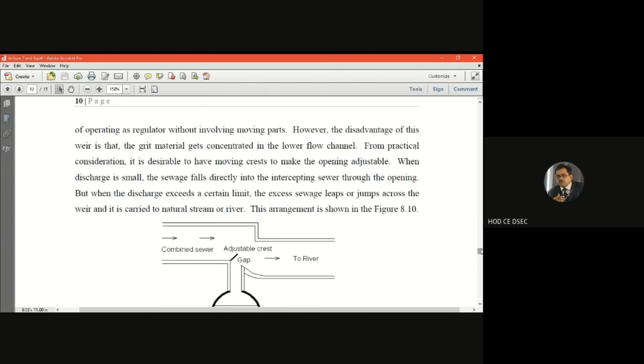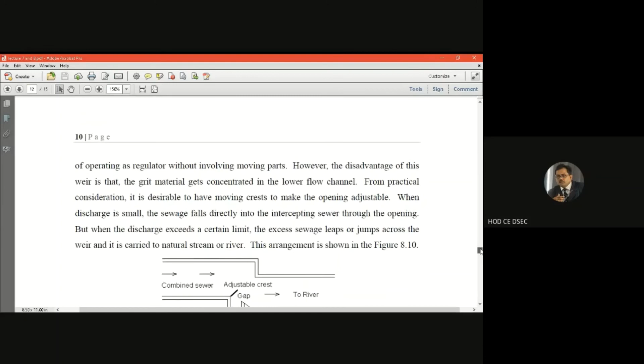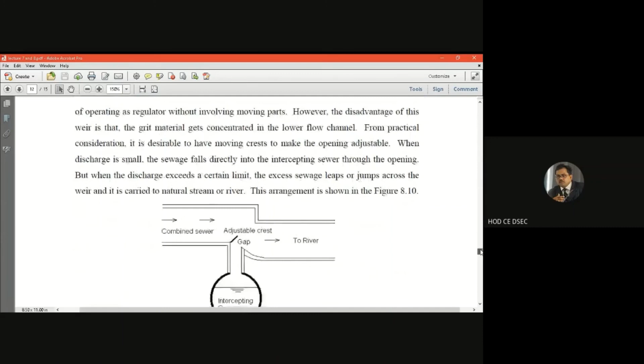So it has an advantageous matter. What advantages? Without involving moving parts, it can regulate the flow. That is the main advantage. Here you can see in the figure that there is no operating regulator. Definitely, it is a regulating device without involving moving parts. But the disadvantage is that the grit materials get concentrated in the lower flow channel. From practical consideration, it is desirable to have a moving crest to make the opening adjustable.